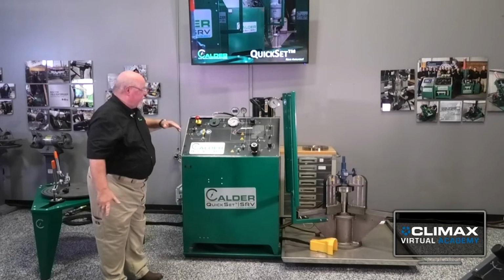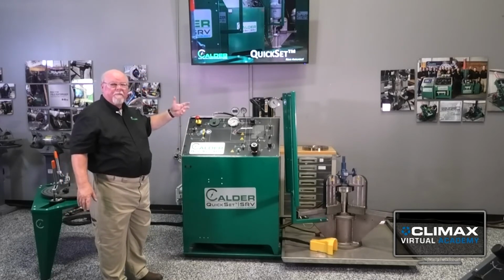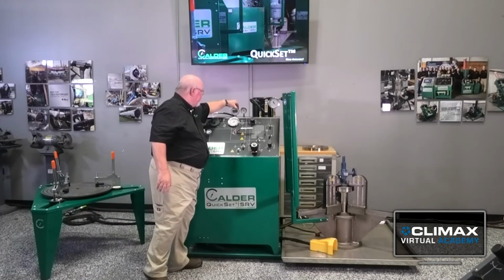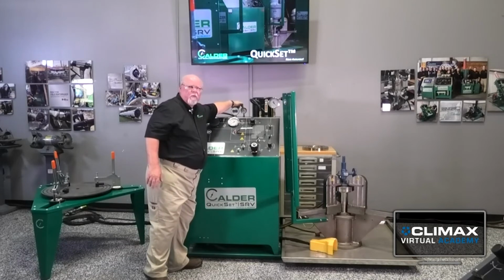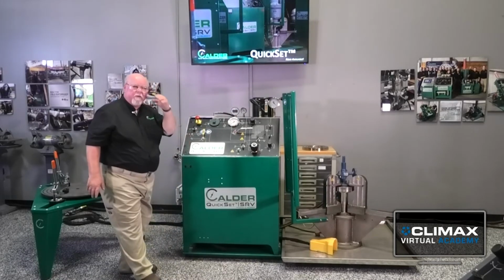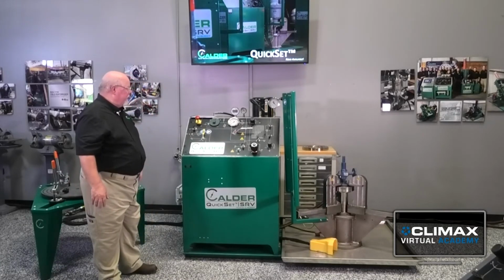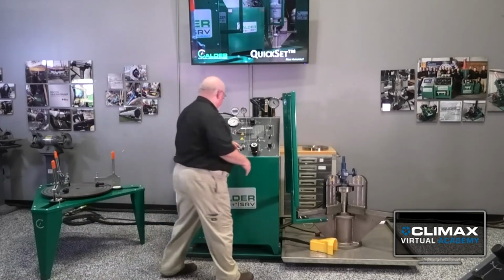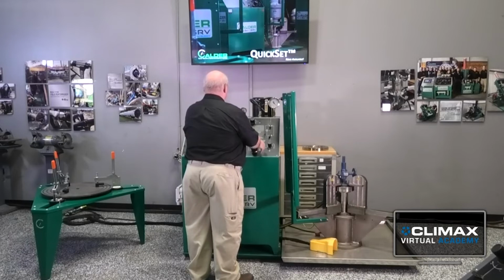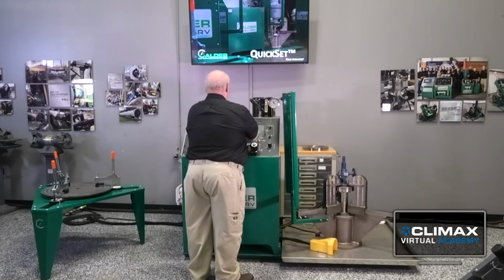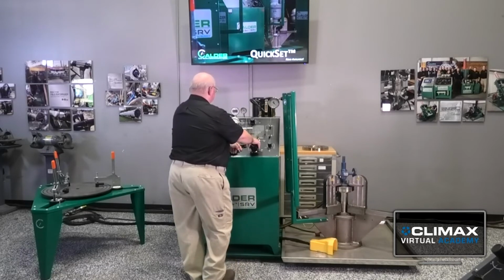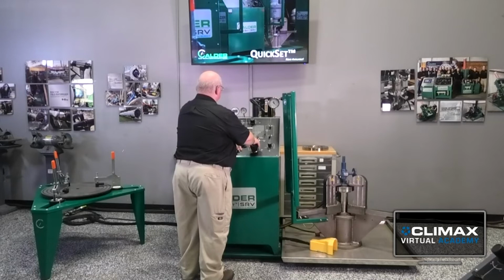Now all I need to do is ensure that I have enough stored pressure in my vessel to provide test fluid. I zero my gauge. I have around 1,500 psi stored at the moment, so with this valve set at 400 psi, that should be more than adequate for me to get tests out of it. So with that, I'm going to go ahead and run a test. Normally we would come up to about 3/4 of the set pressure at whatever speed or ramp rate I want, and then from there I'll start controlling the ramp rate. In this case, with a 400 psi set valve, I'm going to take it up to about 300 psi and then start controlling the ramp rate from there.